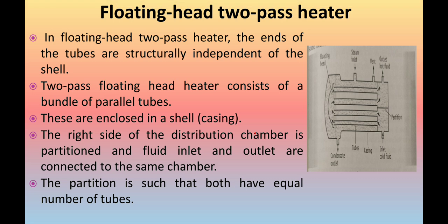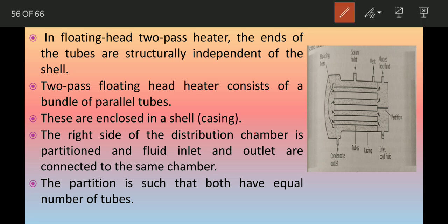Now let's talk about the working. Steam is introduced through the inlet as you can see in the diagram. As the steam flows down the tubes and they get heated, the condensate vapor escapes through the bottom of the shell, and non-condensable gas, if any, escapes through the vent at the top of the shell. Here is your steam inlet; from here you can collect the condensate, and the vent can discharge gas from here.